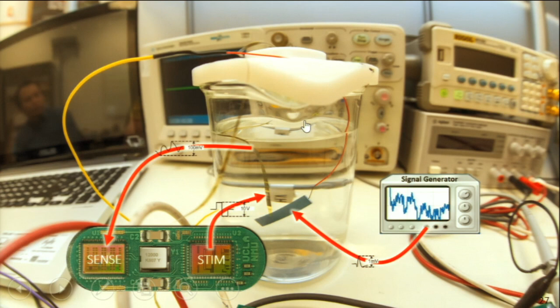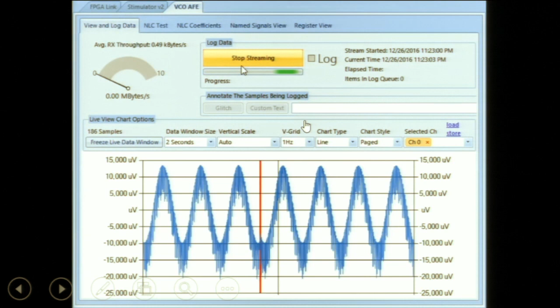This is the user development version on which you have 4 stimulation engines. You can program the amplitude and also decide on which channel it maps. So you can see here 3.1 milliamps on this one that was programmed. You can also program the pulse width and display then the recording of stimulation plus artifacts. All this fuzziness that is riding along this waveform is actually from the stimulation artifact.